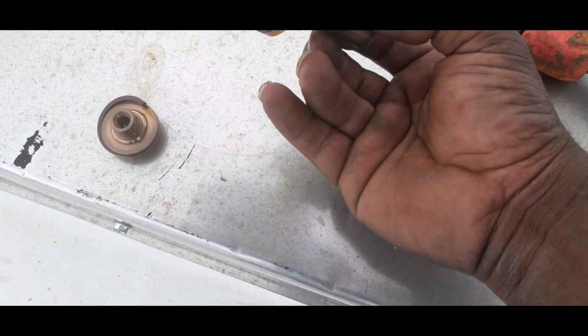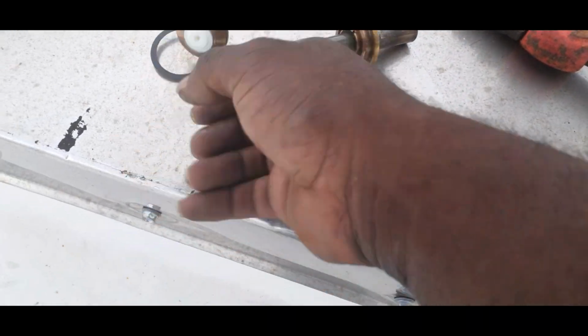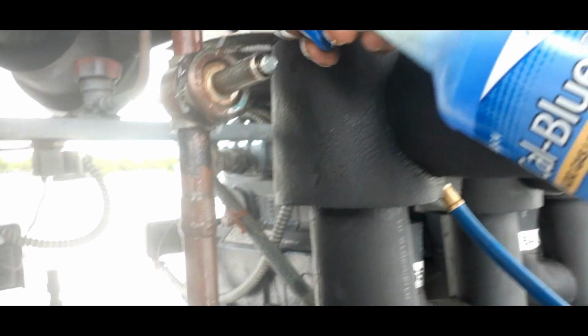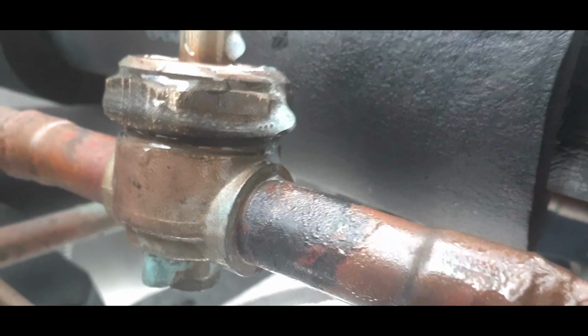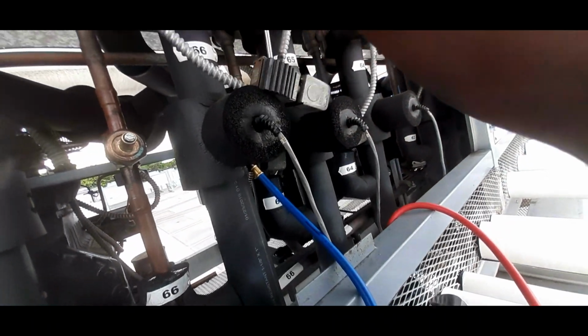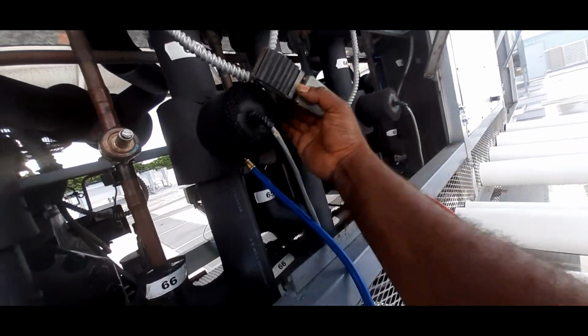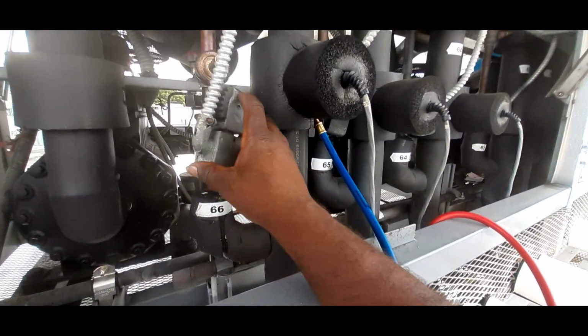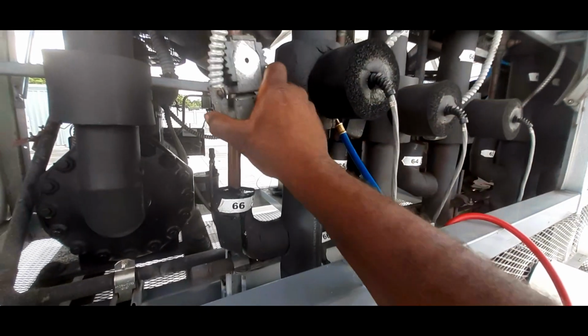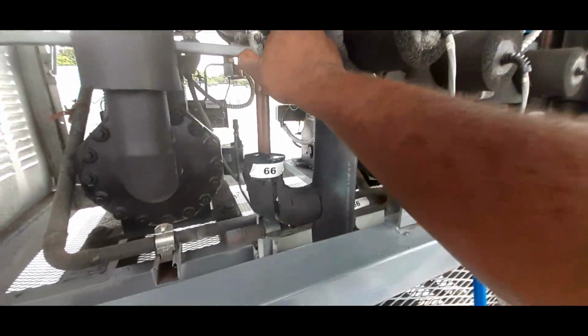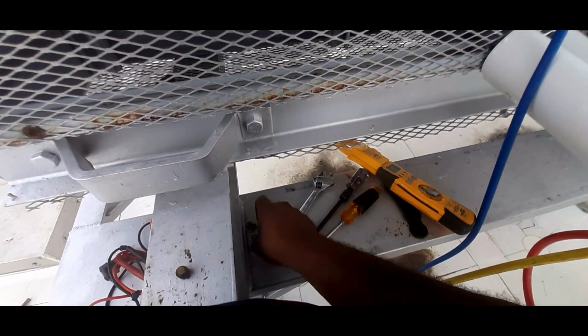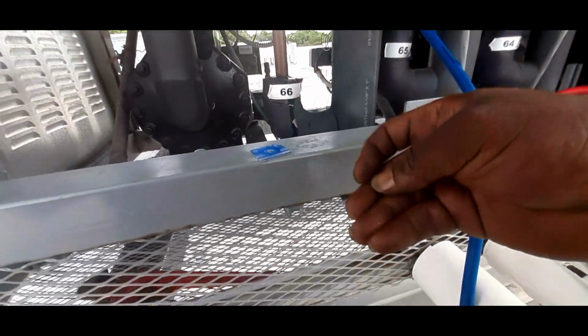Alright, so let's go ahead and tighten up this new one. Got my wrench right here. Let's go ahead and tighten this baby up. Check this baby for leaks. Here's our old rebuild kit right here. This is what was sticking, so just tighten up our new one. I put my screwdriver in there. It is not energized right now. If it was energized, that would have been sticking like a magnet. So we're gonna hang this just like that. Use the screw. Just put my old tag back with the new screw.